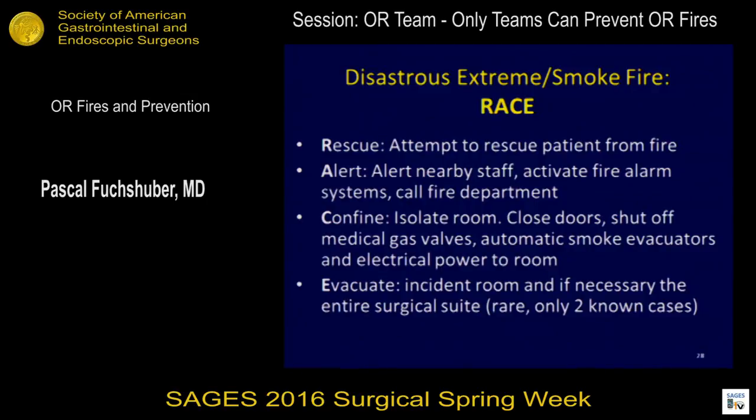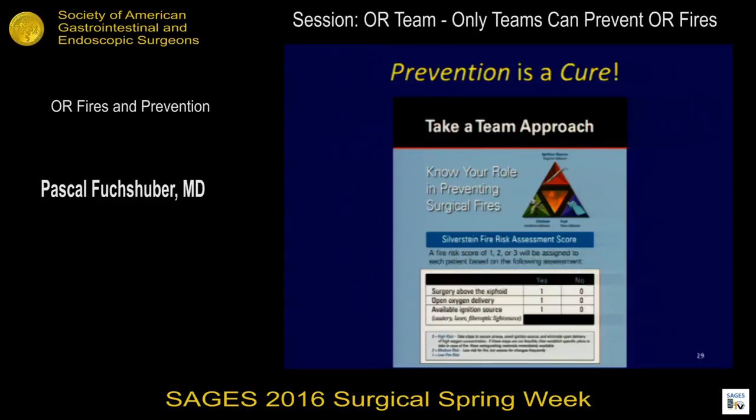Rescue, alert, confine, evacuate — RACE. Rescue the patient, alert nearby staff, isolate the room, close the doors, shut off medical gas valves, and evacuate. There are only two known cases where an entire surgical suite had to be shut down because of a fire. In most situations you are in charge — you can change it, you need to react, you don't need the whole hospital to react. Take a team approach. There are risk assessment scores, especially if you do head and neck surgery, that you can integrate into your timeout, and that will inform the entire team.